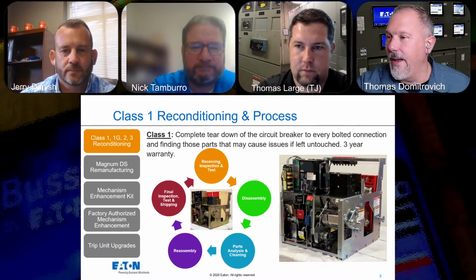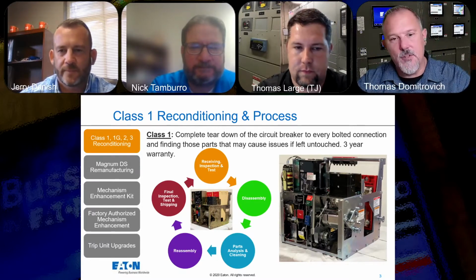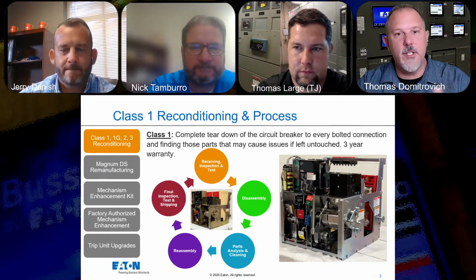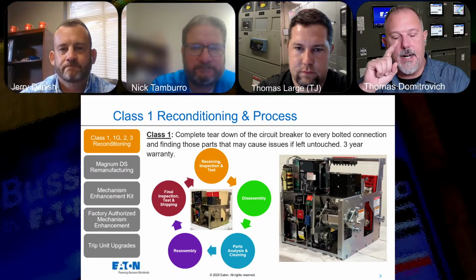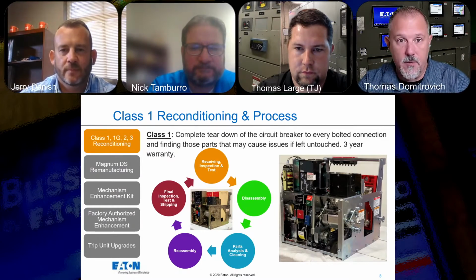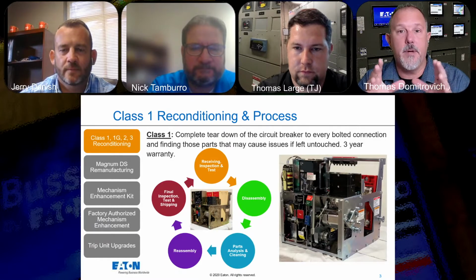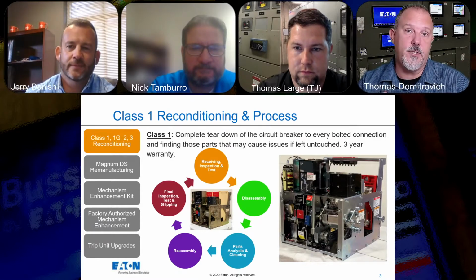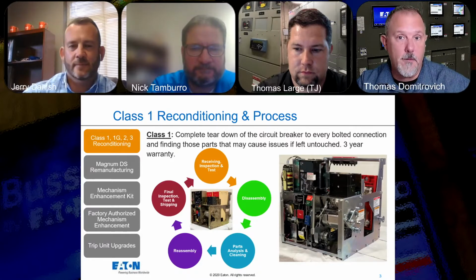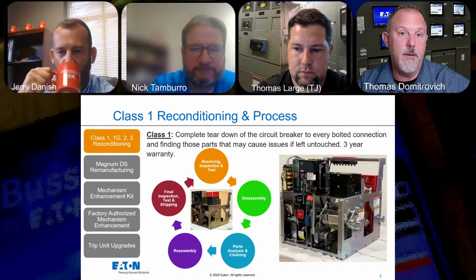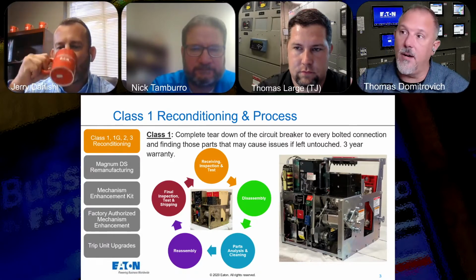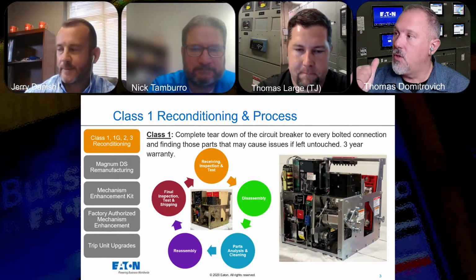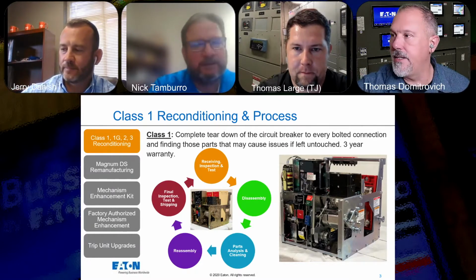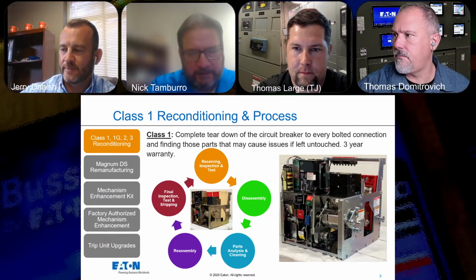Excellent. Okay, cool. So I can get the same voltage rating, same current ratings, different trip characteristics. I can add all the functions of communications, arc reduction, maintenance switch, zone selective interlocking, all that great stuff. I have the same interrupting rating, but to your point, TJ, and what we talked about yesterday, I could increase the SCCR rating of an assembly with an evaluation, but that's not what we're talking about here. Cool. And I can make it look like it's brand new. I love it.